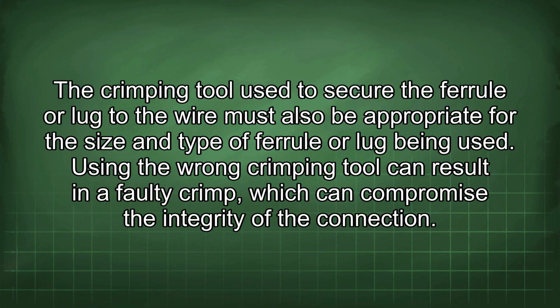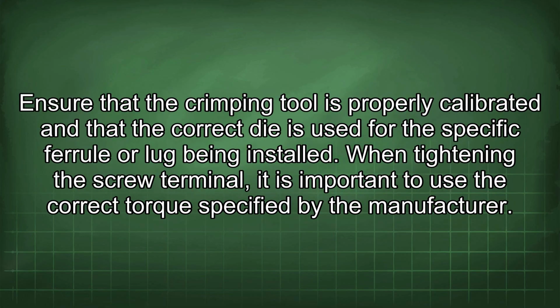The crimping tool used to secure the ferrule or lug to the wire must also be appropriate for the size and type of ferrule or lug being used. Using the wrong crimping tool can result in a faulty crimp, which can compromise the integrity of the connection. Ensure that the crimping tool is properly calibrated and that the correct die is used for the specific ferrule or lug being installed. When tightening the screw terminal, it is important to use the correct torque specified by the manufacturer.